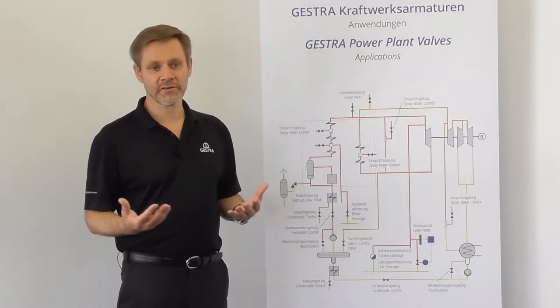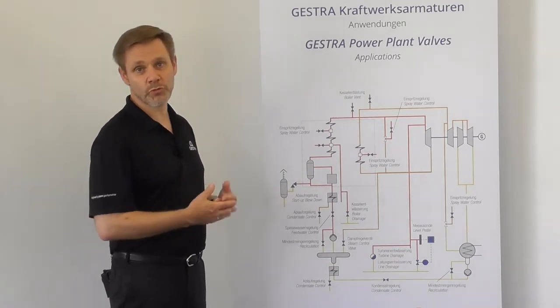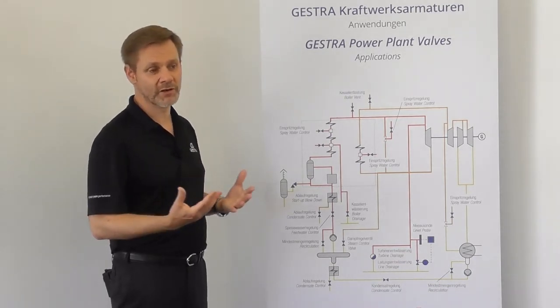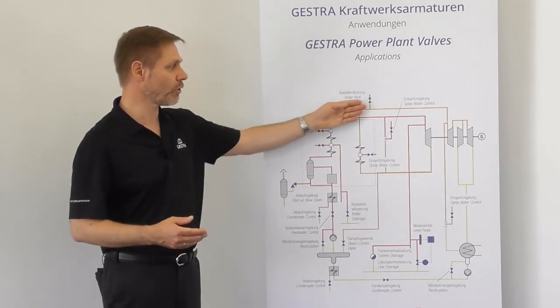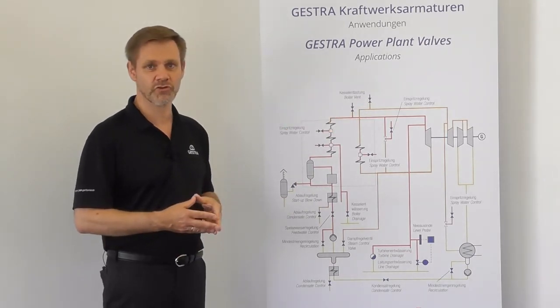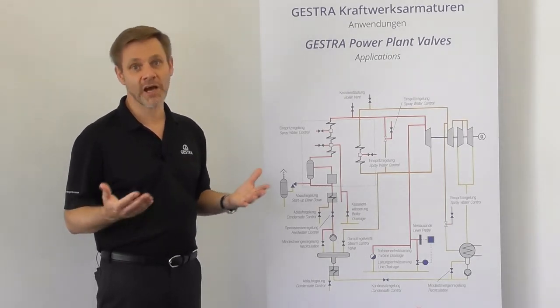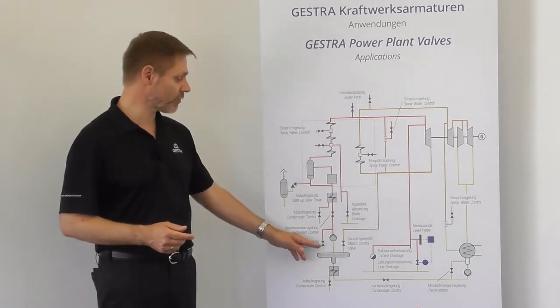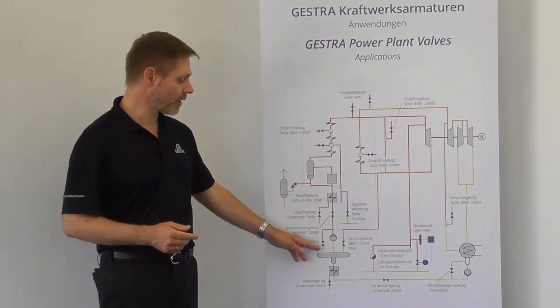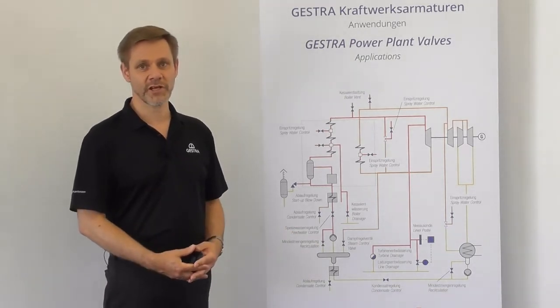We also have high pressure steam control valves which have to handle high differential pressures. These are for instance the boiler vent valves at the high pressure steam lines. The application which faces the highest differential pressure in the boiler is the feed pump recirculation valve where power stations often have problems with cavitation damages.